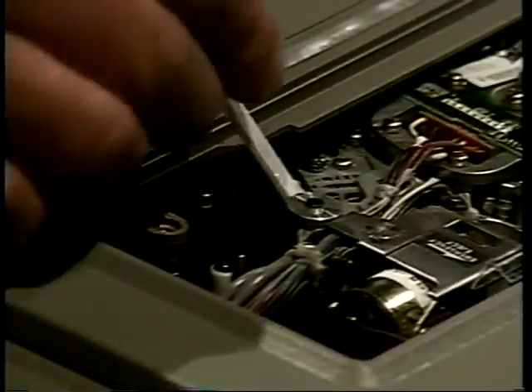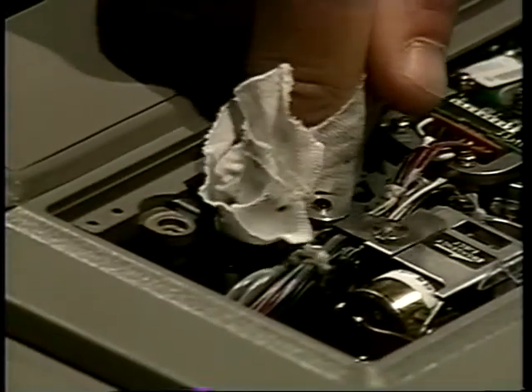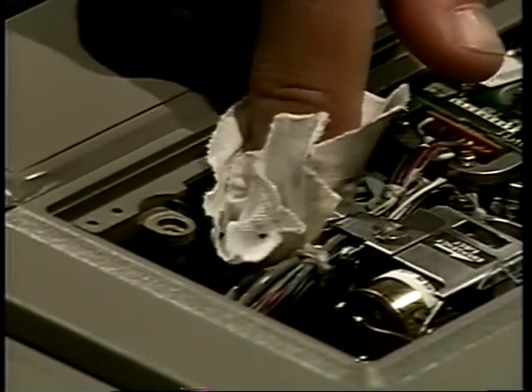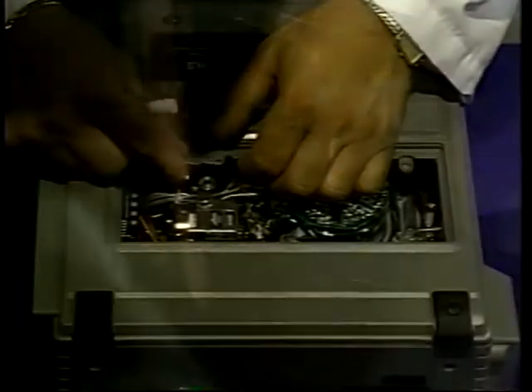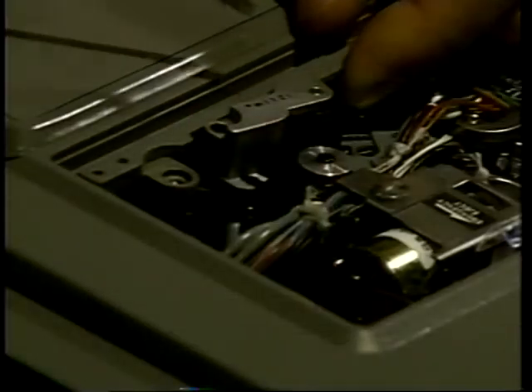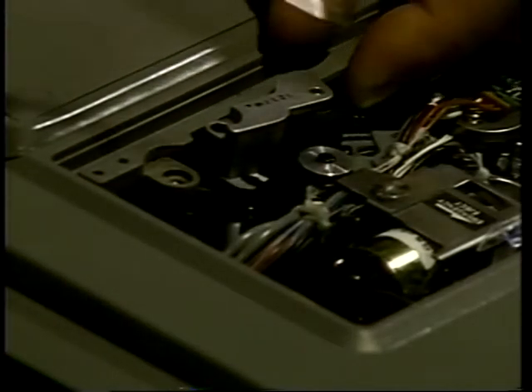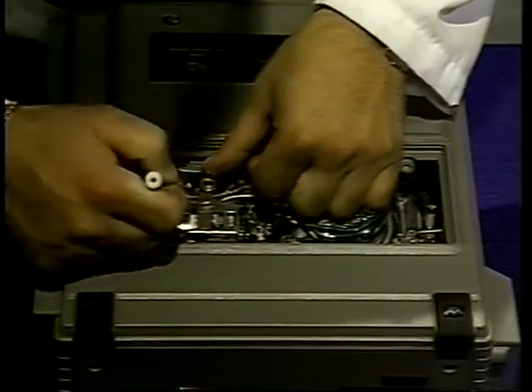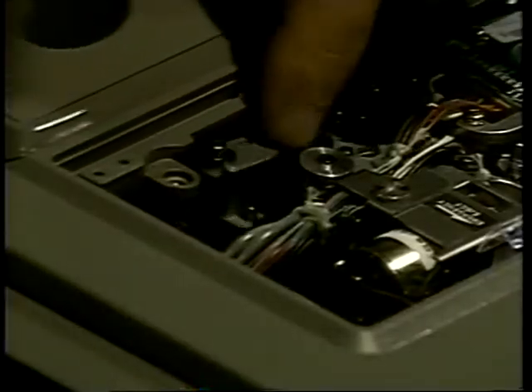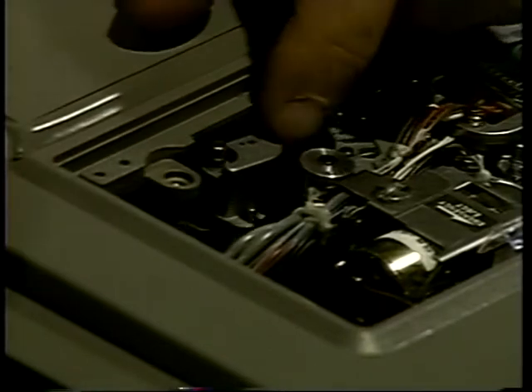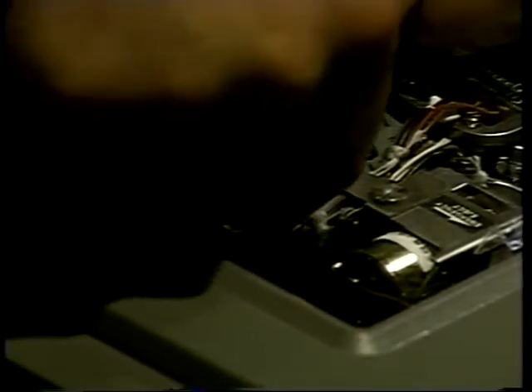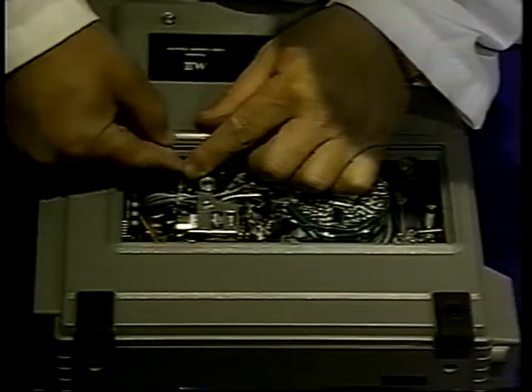Clean inside the AC stack with the cleaning stick. An alternative method is to clean the AC stack with the Tex wipe as before. On the inside of the AC stack, it's important to clean under the plate. Be careful not to pick up and transfer grease in this area. Replace the pinch roller, being careful that it doesn't get caught here and that it fits in the guide. Make sure that it moves up and down. Push the pinch roller down and install the E-ring, as shown here. Make sure it doesn't come off.